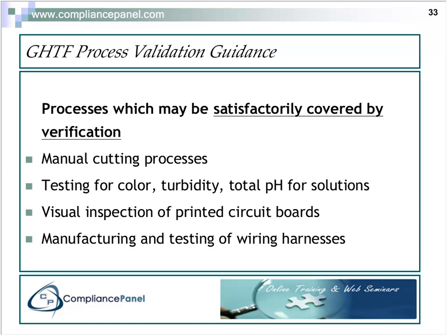Okay, for those printed circuit boards, there are certain workmanship standards that you can measure against for verification, but again, the FDA does have some very specific leanings towards, hey, we want those soldering processes to be validated. Now, I think here we're talking about visual inspection of the copper-plated board before the components are installed and soldered.